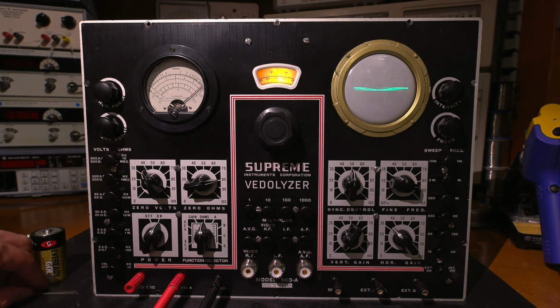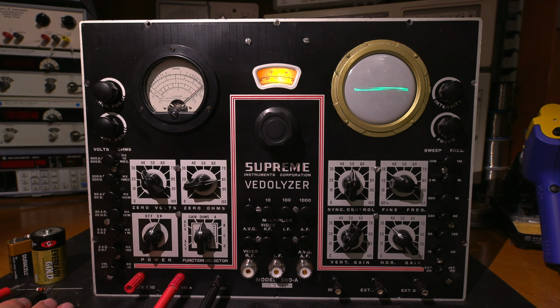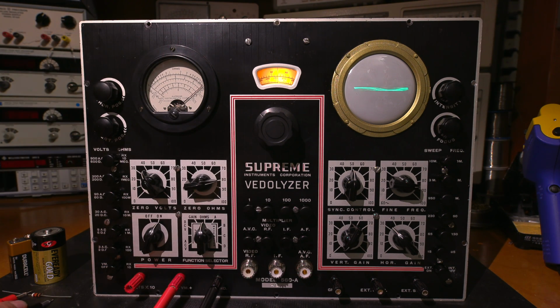I'll put this on here so I don't have to touch anything, so I don't want to add to the resistance. And that should point right to that 1, right on that 1 line right there, if this is reading correctly. Look at that. This thing really doesn't need that much of an alignment, does it? It can be touched up just a little bit, but that's extremely close. Looking at it straight on, it's pretty much right on the 1. It's actually about a needle's width below the 1, which isn't too bad.